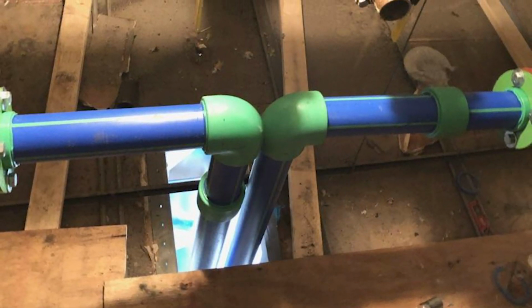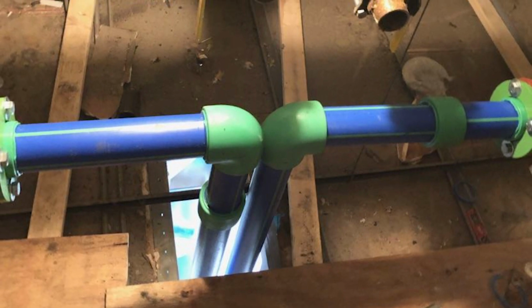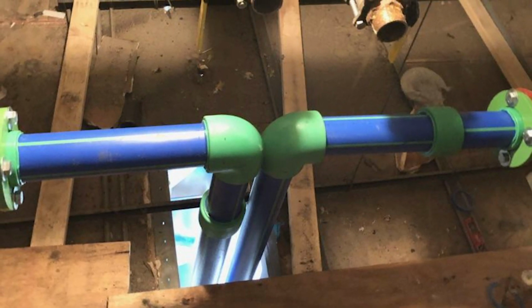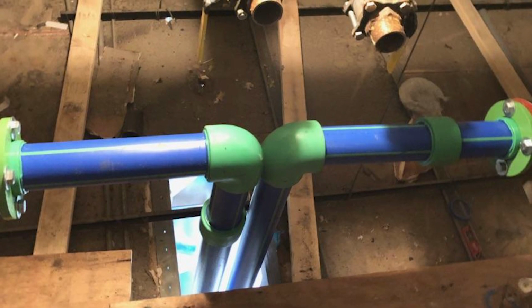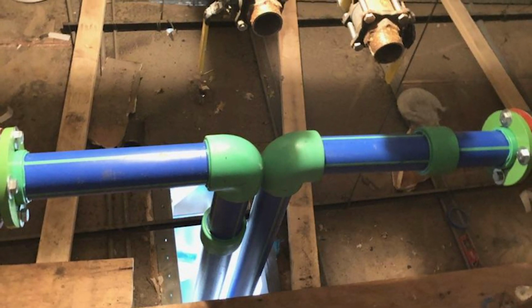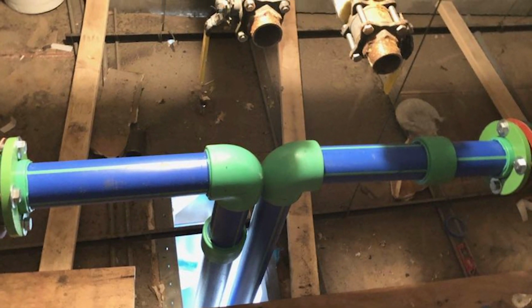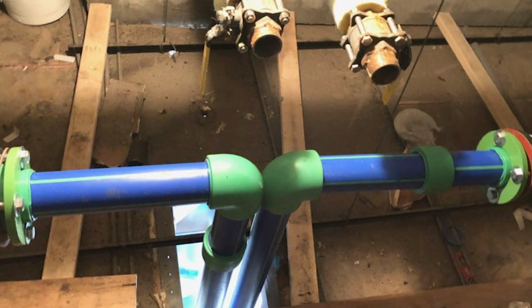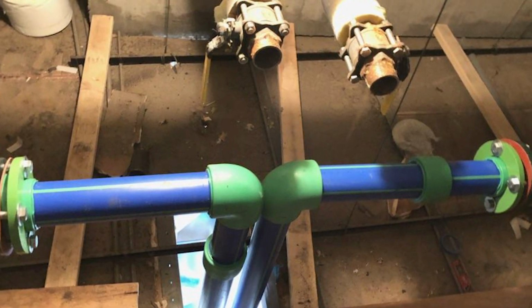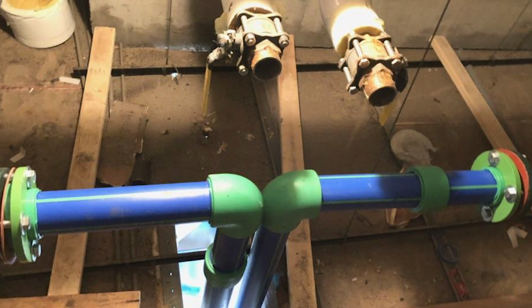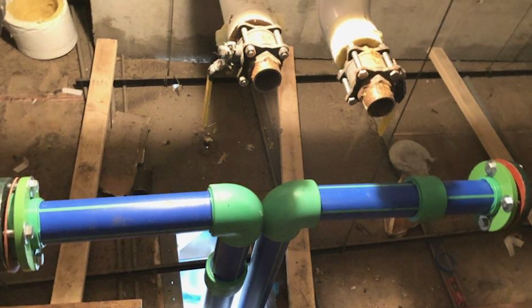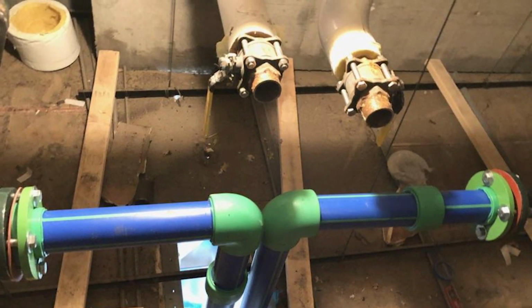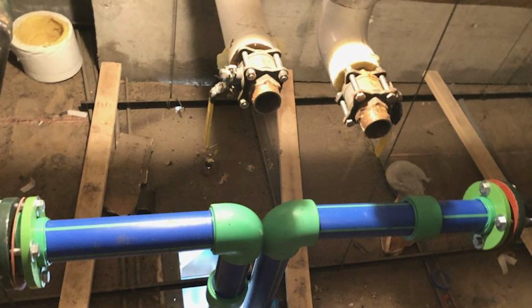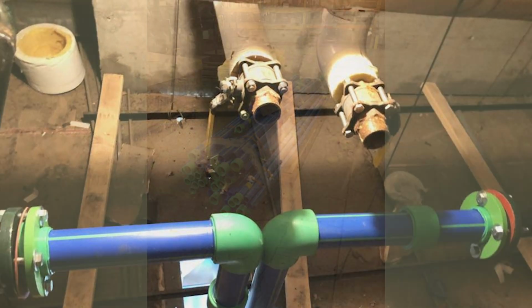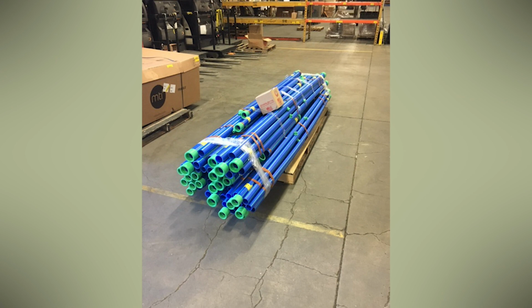The 16 sets of risers were fabricated off site at a facility in Fulton, Massachusetts belonging to Ferguson, the largest wholesale distributor of residential and commercial plumbing supplies and pipes, valves, and fittings in the U.S. The risers consisted of 1¼ inch through 4-inch pipe with 3/4 inch runouts. The system ended up with more than 4,000 joints. On a typical solder job, you can expect around 3% leaks, which means 120 leaks. This system had just 5.